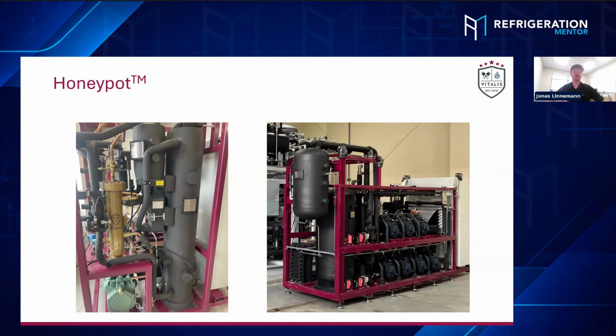And once you're done with that, you have the system pre-filled. You would start to fill your vapor to get above the triple point to not run into dry ice issues. And then you would just start to fill the system with liquid into the liquid line or the liquid receiver, right? And that's totally good to start up the system. And if there's some oil missing inside the compressors, as soon as you fill the system, the compressor should be filled with the oil level regulators as well.